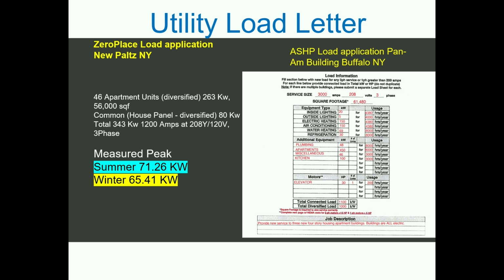But the bottom line is, the load letter was about 1,100 kW for one of the apartments. The load application for Zero Place, thanks to GEO, was about 340 kW, 1/3 of that. And the actual consumption was about 65 kW in the winter. Less than 6% of what the load applications were for an air source heat pump driven building. Now this is design versus reality, and if you can accept, this is over designed, I get this.